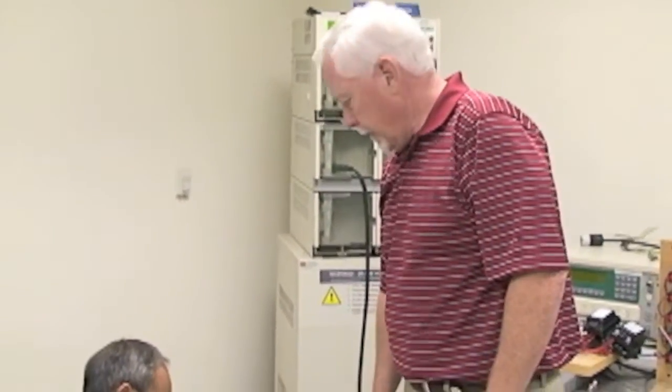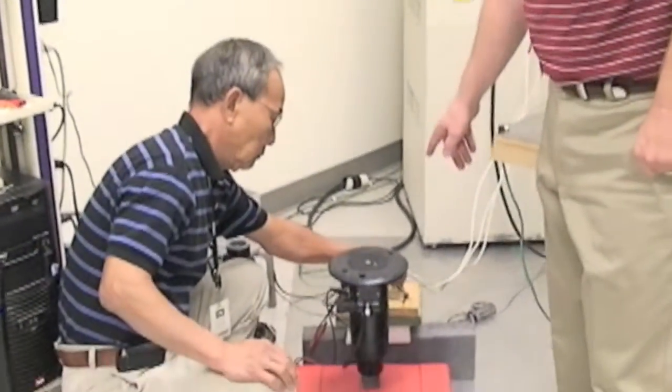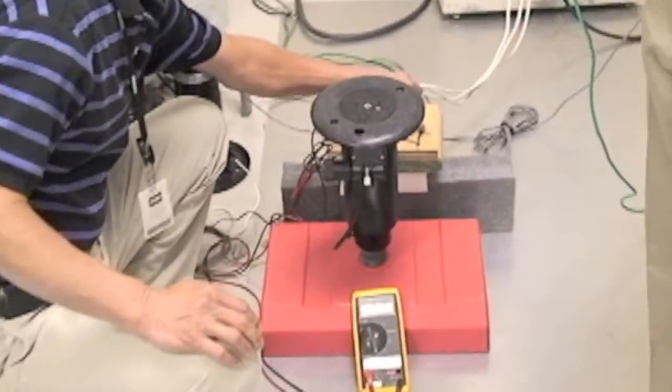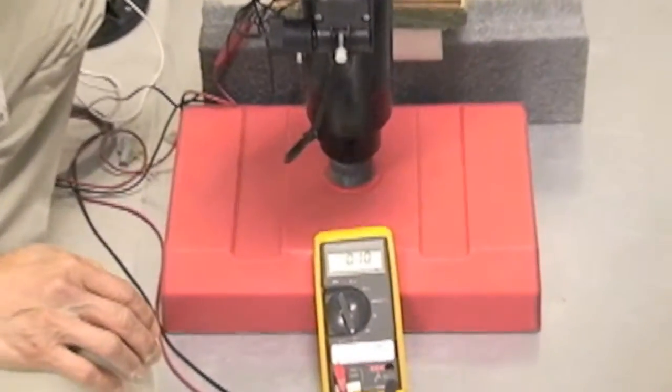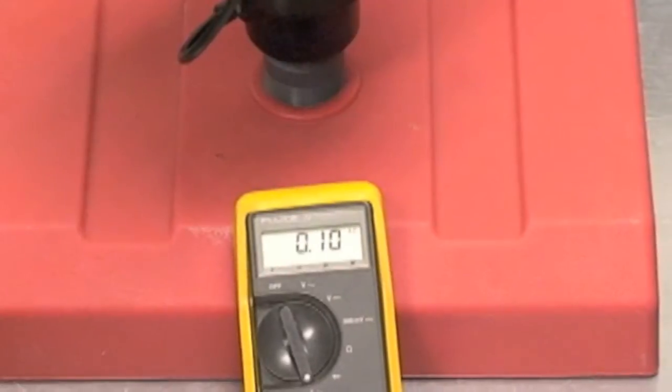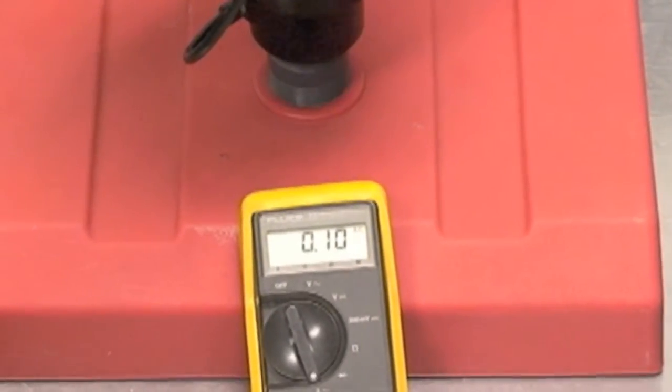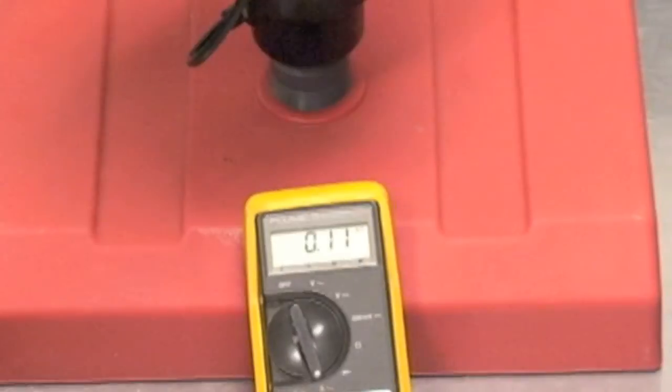Okay. So after being subjected to four 20,000 volt lightning strike simulations we're now applying 24 volts across the solenoid and you can see that we have the exact same current draw of 0.1 amp as we got prior to the test.